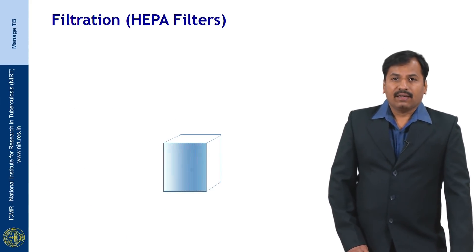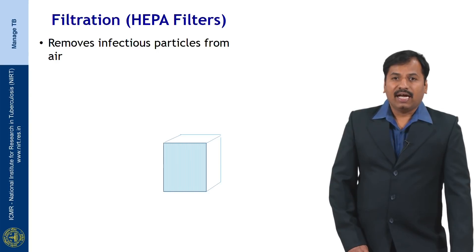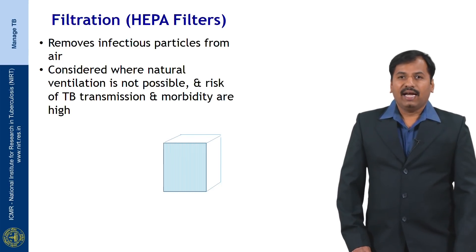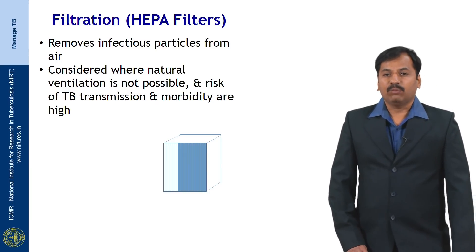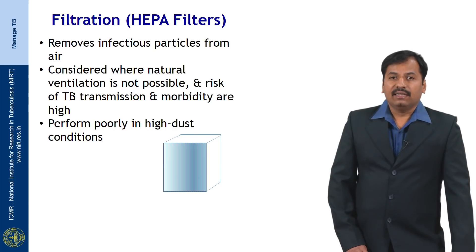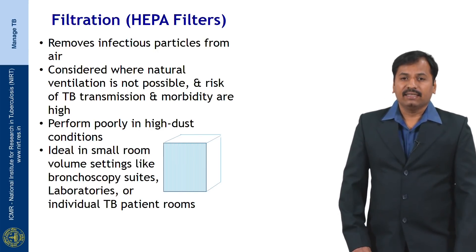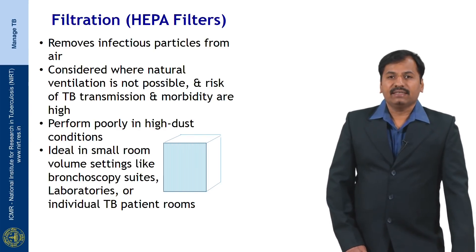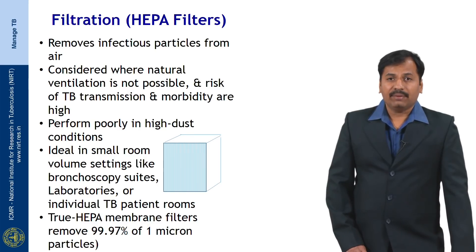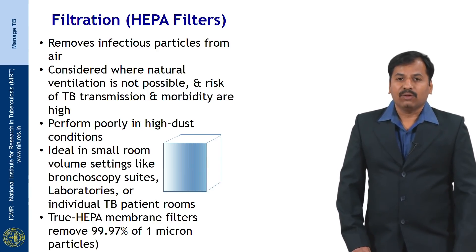HEPA filter is a kind of high efficiency particulate air filter. It removes infectious particles from air and is considered where natural ventilation is not possible and risk of TB transmission and morbidity are high. It is not advisable in high dust conditions but is ideal in small room settings like bronchoscopy suites, laboratories and individual TB patient rooms. True HEPA filters remove 99.97 percent of particles less than 1 micron in size.